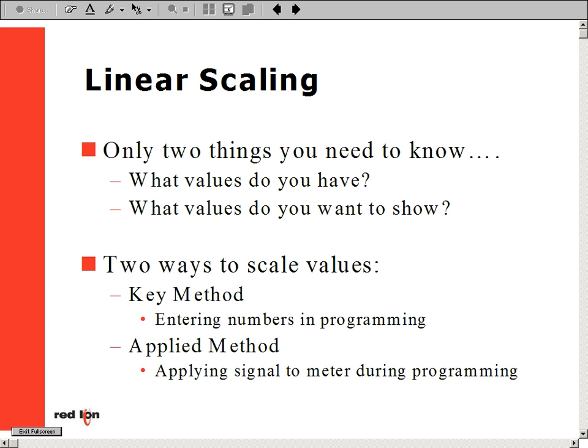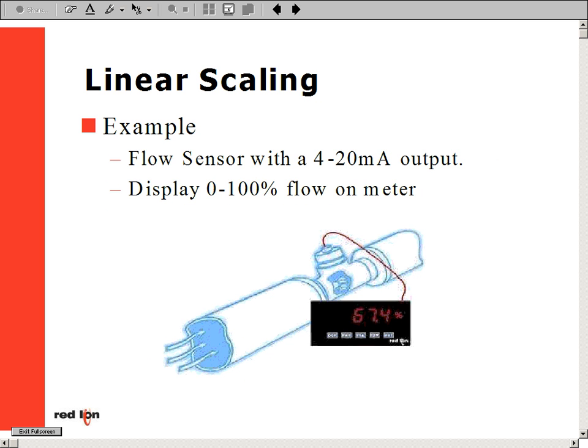The first step is to select the proper scaling method: key in or applied. The next step is to key in or apply the low input signal. In our example, that would be 4 milliamps. Next, in step 3, we key in our corresponding display reading for the low point, or in our example, 0%.